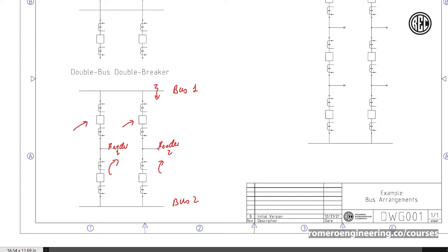Likewise, if we wanted to take one of the two buses out for maintenance or work on a specific breaker, we can isolate one bus and continue feeding the feeders through the other bus. This is the double bus, double breaker configuration. Of course, now we have more breakers per transmission line or feeder — for feeder one, for example, we have two breakers. This is a more expensive design, but you gain the flexibility to isolate one bus without interrupting service to the feeders or transmission lines.